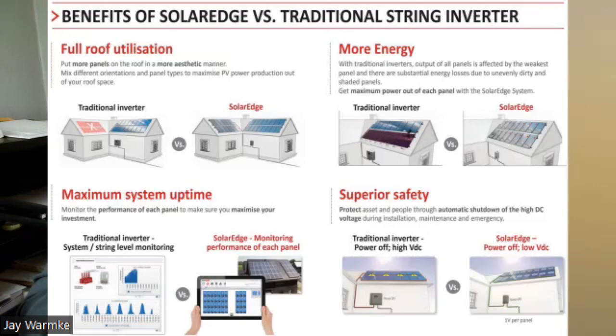And the same thing with a string inverter: if one of the panels in the string is bad, it's going to throttle down production for the entire string. So if one panel is shaded, it affects all panels in the string. That's one of the real strong arguments for module level power electronics. And most string inverter systems now have module level power electronics that you can add to the system, and they can do any or all of the things that an optimizer does. Not a microinverter, they wouldn't do that. But essentially, the main thing an optimizer controls at the panel level is maximum power point, so you're getting the best production at each panel, given that panel's individual environment. So it deals with shading, it deals with whatever. It treats them all differently, so you're not getting the string impacted by all the panels in that string.